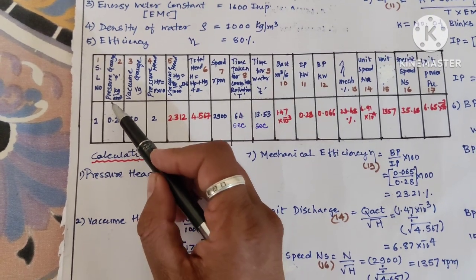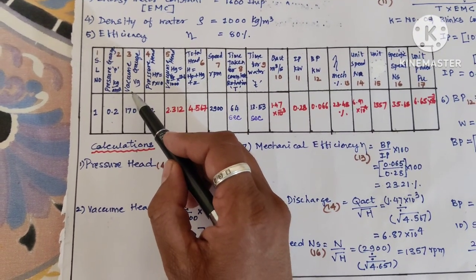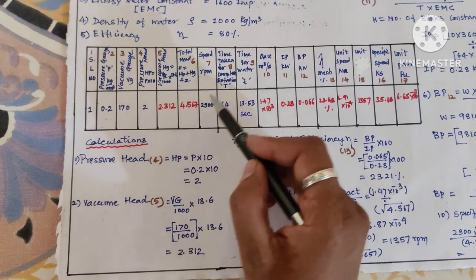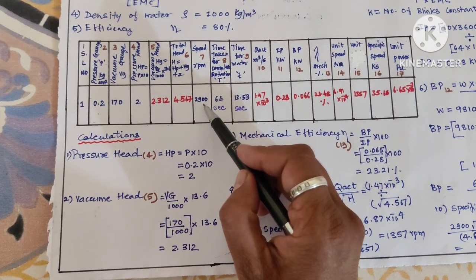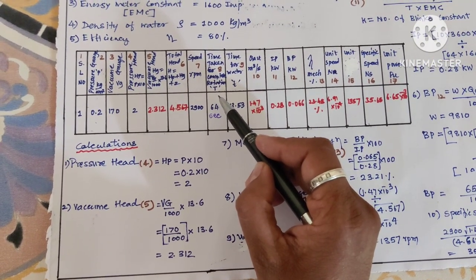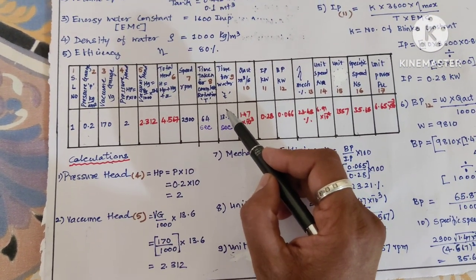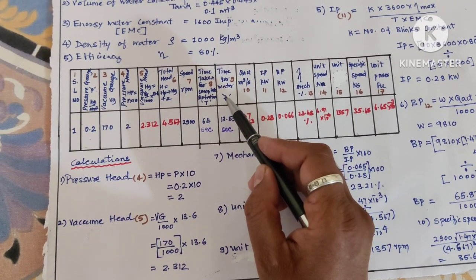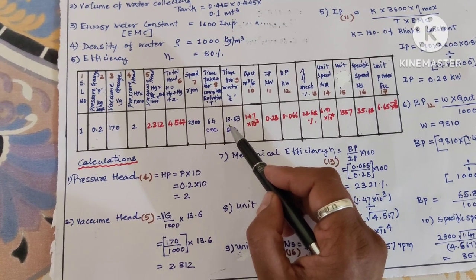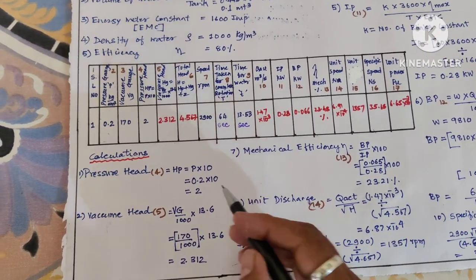0.2 is the reading shown on pressure gauge, 170 is the reading shown on vacuum gauge, the speed is 2900 rpm. For 10 blinks of energy meter it is taking 64 seconds, and to collect 20 liters of water in the tank it is taking 13.53 seconds.